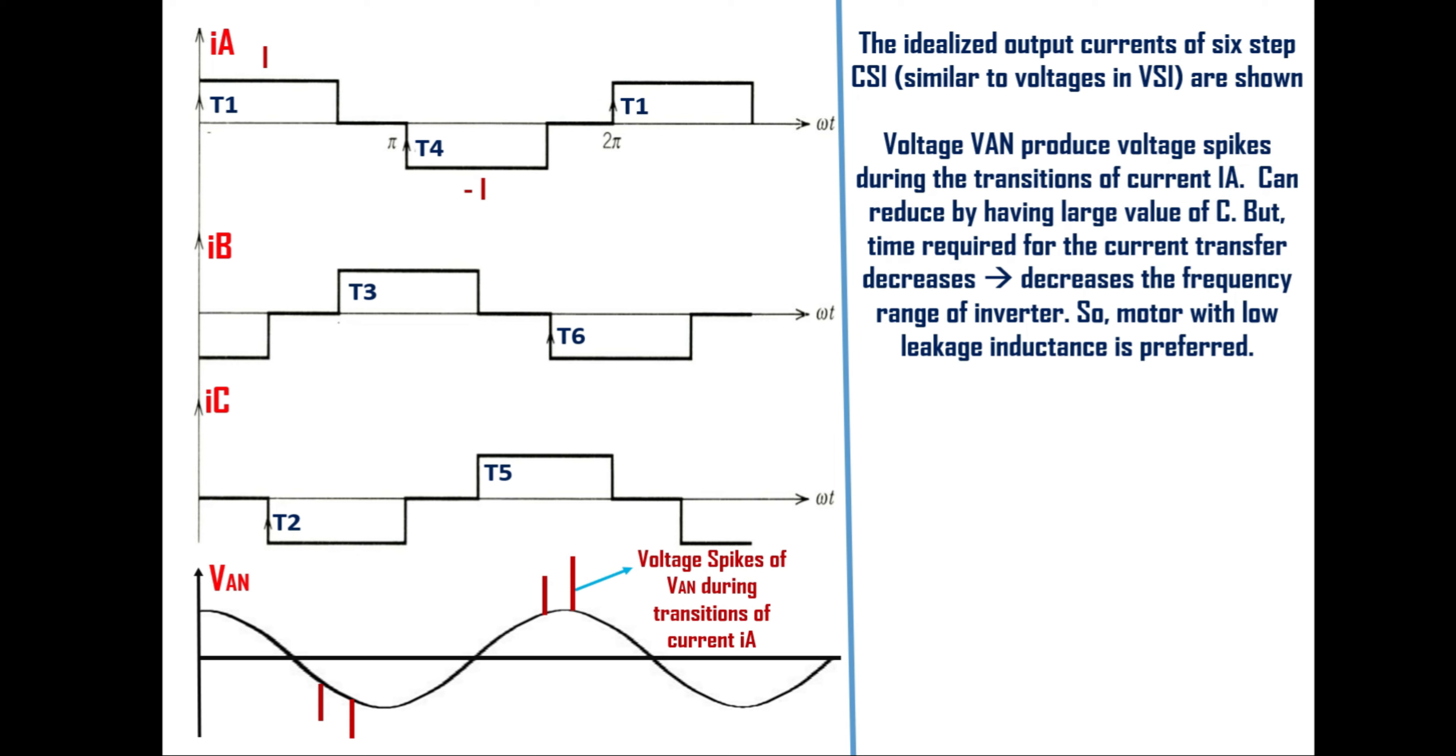Phase voltage Van will be sinusoidal and produce voltage spikes during the transition of current Ia. This voltage spikes can reduce by having large value of capacitors. But if you use large value of capacitors then time required for the current transfer will decreases which in turn will decreases the frequency range of the inverter and hence the speed range of the motor. So usually induction motor with low leakage inductance is preferred for current source inverter.